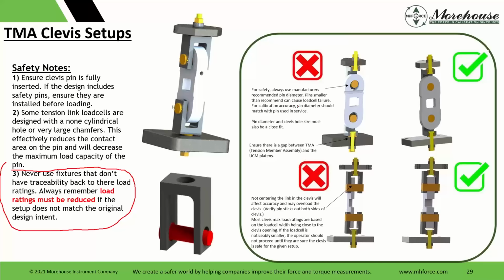Yeah. And always use the manufacturer's recommended pin diameter. Pins smaller than recommended can cause load cell failure. For any calibration accuracy, pin diameter should match. And that's what we started with on the accuracy. So if you do not use the proper pin size, not only are you going to be in large error, that you could adjust and introduce and pass on huge bias to your unsuspecting customer, but your technicians and the people making the measurements could be at risk of the clevis breaking. And when that happens, objects could potentially fly and hurt them.